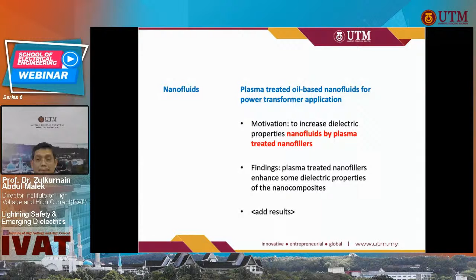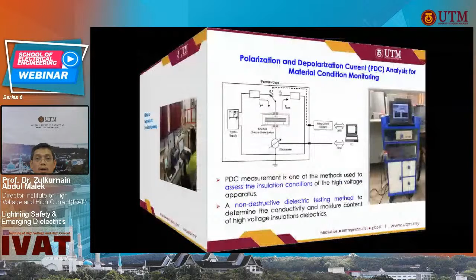This is because even at normal operating voltage, the dielectrics are continuously stressed, and as you know, partial discharge occurs even at operating voltage. So it is very important for us to detect any problem with insulation in advance. One of the techniques that we can use, and this is a non-destructive technique, is called polarization and depolarization current. And we developed this equipment in our lab.